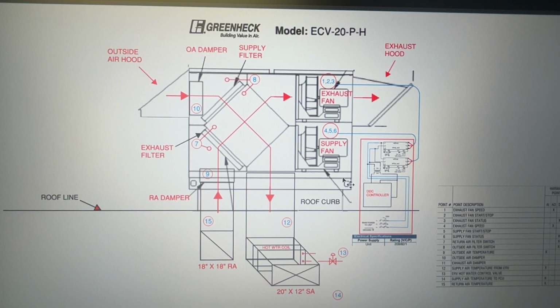Let's get into the main parts of it and then we'll get into the details. So this unit has an outside air hood here. You have your outside air damper, your supply air filter, and this is your enthalpy core. This is where the two air streams cross one another. Now they don't contaminate each other, but across that core they do absorb or reject heat, depending on how you want to look at it.